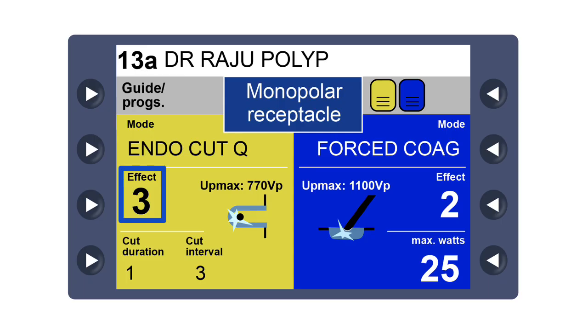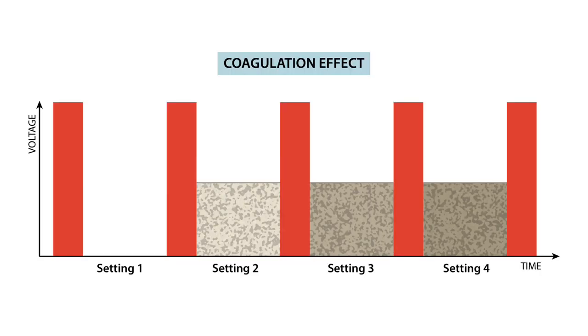When it comes to cutting the polyp, you should understand what these three things mean: effect, duration, interval. Let us learn about effect. There are 4 settings for effect. Setting 1, that means there is no coagulation in between those red bars that indicate cut. Setting 2, effect 2 gives a soft coagulation in between the cuts. Effect 3, that is setting 3, delivers a forced coagulation in between cuts. We usually, in endoscopic surgery, go up to effect 3. We don't go up to 4. But if you use 4, you'll have more coagulation.